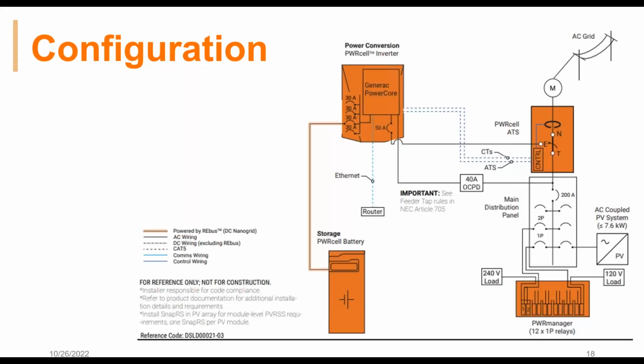Can you use existing ATS that are not PowerCell? Okay, you might be referencing Gen integration here. As long as it's a Generac transfer switch, and for Gen integration, it needs to be the Evolution. It needs to have an Evolution controller, which is most of our gens for the past few years. We would just want to update the control board in the Generac ATS so that it's compatible with PowerCell for Gen integration. So technically, yes, if you're asking about generator integration, you can use a Generac transfer switch that is not specifically the PowerCell ATS, but I'm going to get you a control board that essentially turns a non-PowerCell ATS into a PowerCell ATS. It's a really good question.